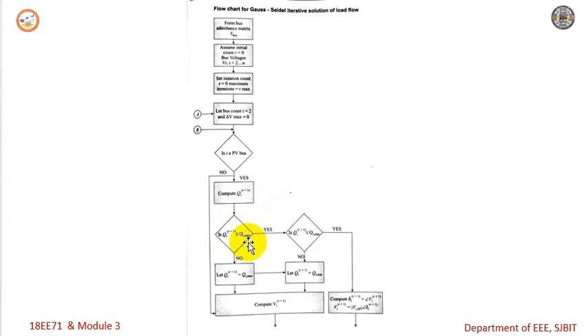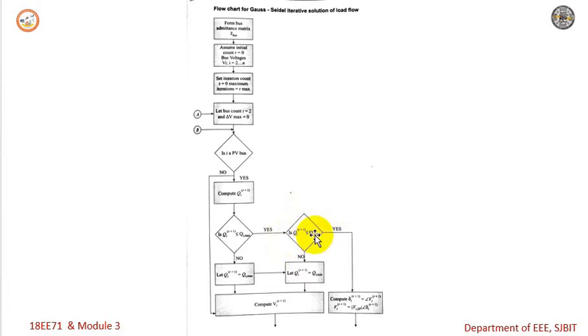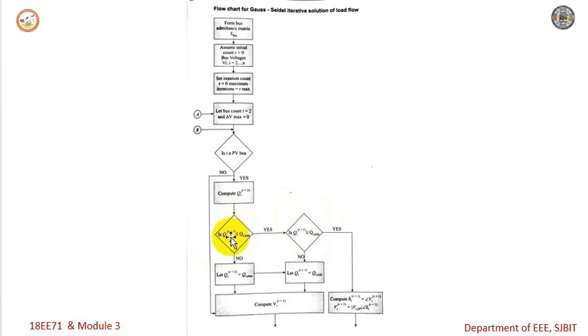First, check the maximum limit: if the calculated Q_i for iteration r+1 is less than Q_i max, then check the minimum limit. If the calculated Q_i value is greater than Q_i minimum, the computed Q_i for the PV bus is retained and we proceed to compute the angle delta, that is, compute delta_i.